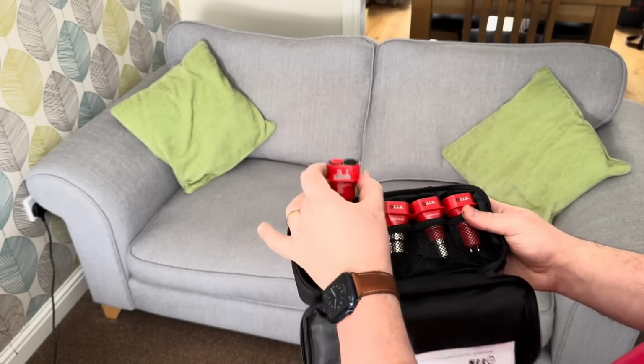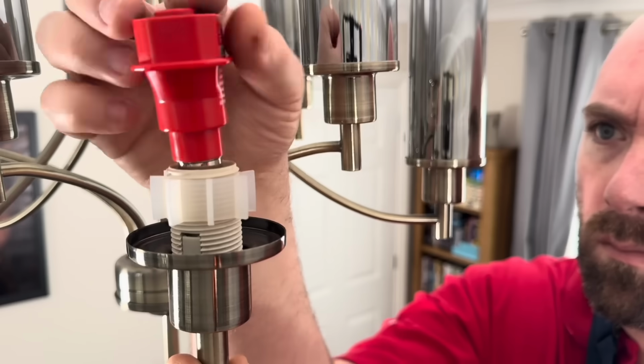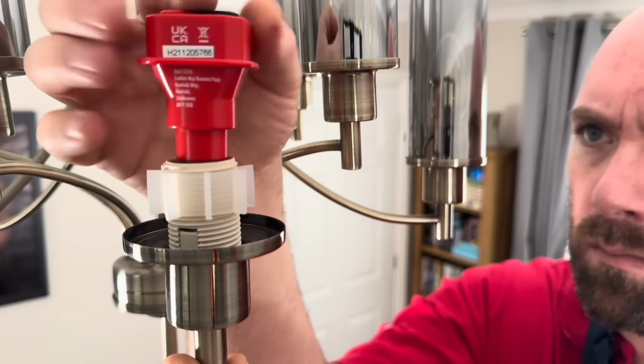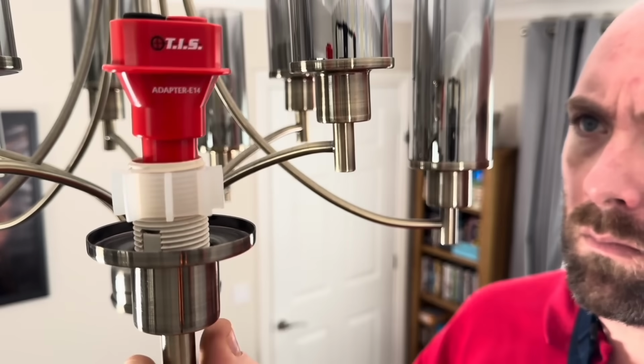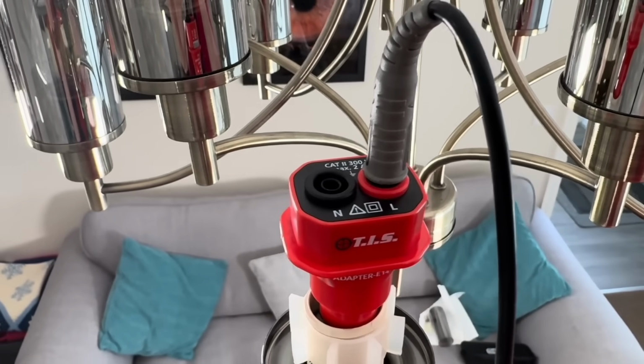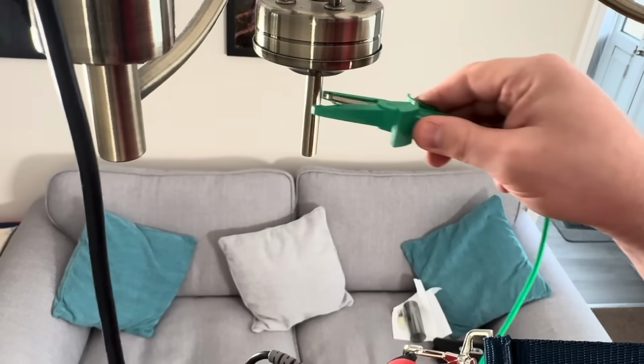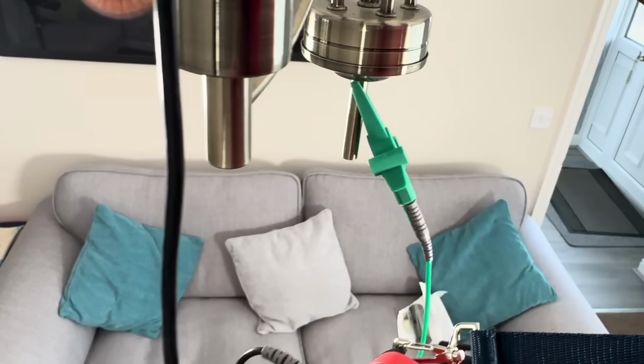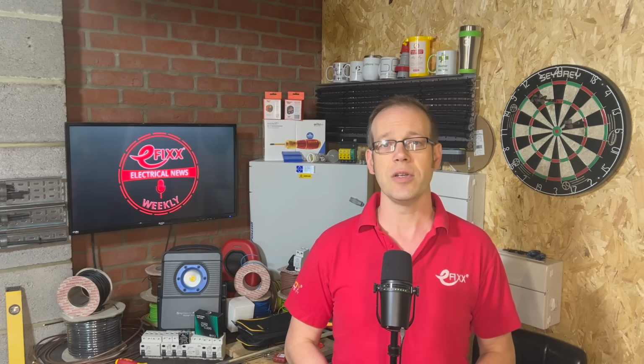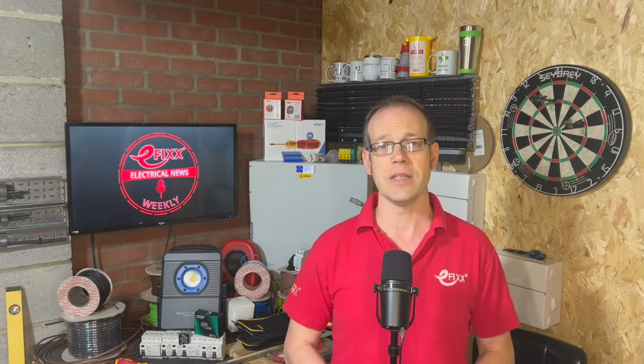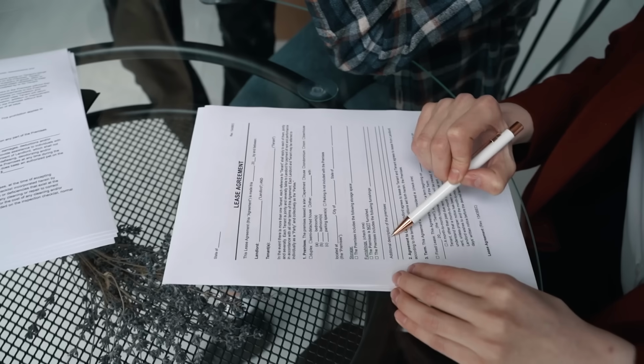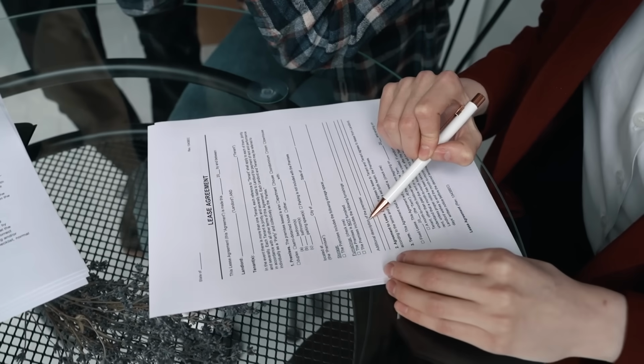A valid cert must be provided to new tenants when they move in, and to existing tenants within 28 days of an inspection. Last month, the government announced that electrical testing would become compulsory in social homes from November. Local authorities and housing associations in England must now conduct tests with qualified and competent persons at least once every 5 years. This brings the sector into line with private rented accommodation.